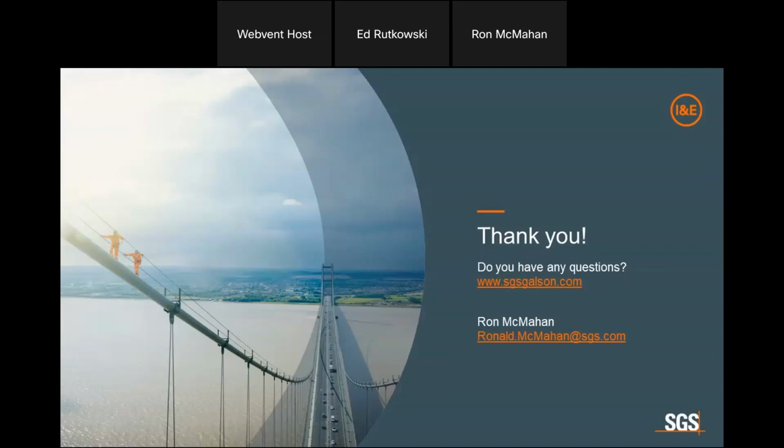So, you need to make a good claim that makes sense. If you're not calibrating and you're not checking, how can you ever even get close to the claim? Our claim was plus or minus 20% of reading across the range. And now as we've gone through calibration and we see the accuracy of these devices, we'll tighten that up.